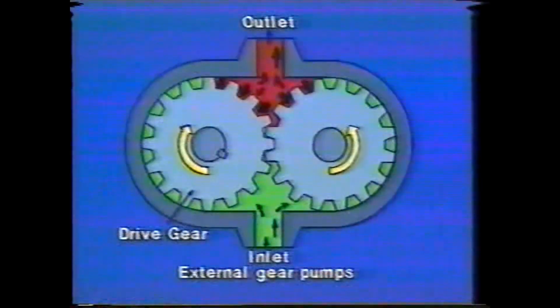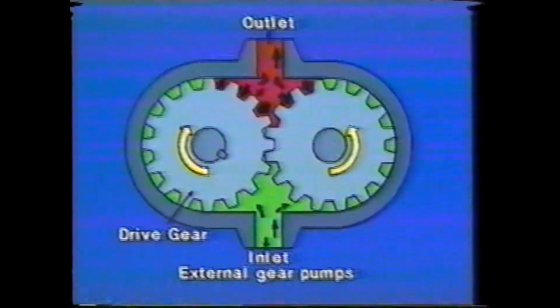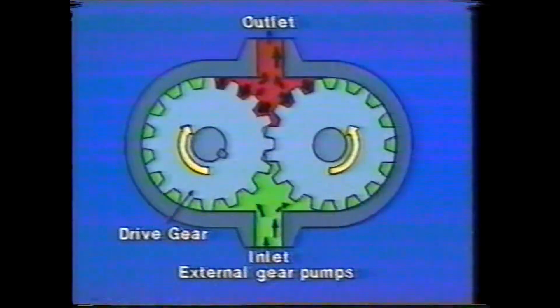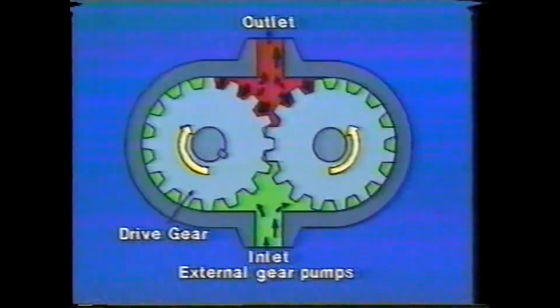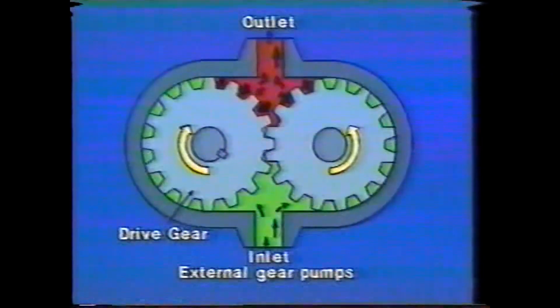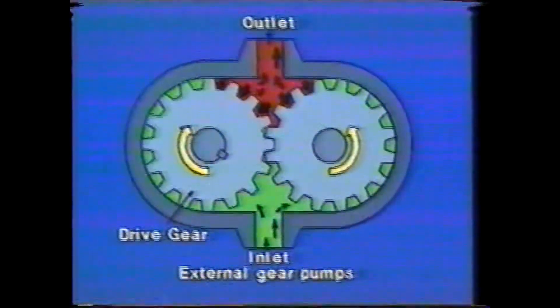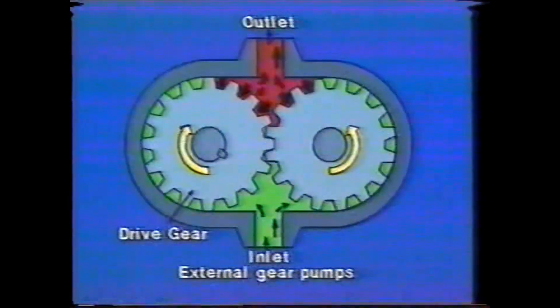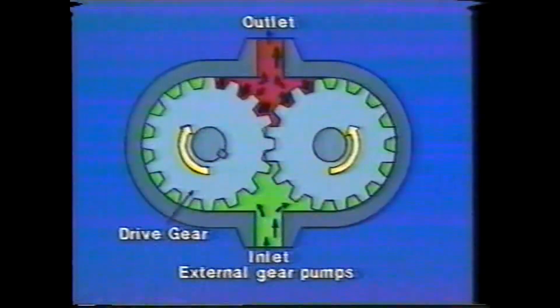One gear, driven by the drive shaft, meshes with and rotates another, called the driven gear. Both are contained within a close-fitting housing. A partial vacuum is created at the inlet as the gear teeth unmesh and fluid flows in to fill the void. Then the fluid is carried around the gears to the pump outlet. As the teeth go back into mesh, oil is forced out through the outlet port. We now have high pressure at the outlet and less than atmospheric pressure at the inlet. This condition is referred to as unbalanced hydraulic loading.